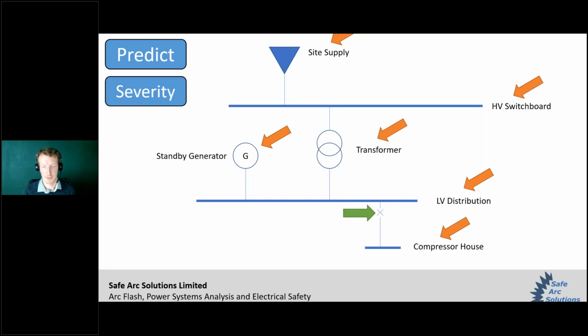And realistically, you also need to think about different configurations of the network. This can really change how the arc flash energy works, depending on whether you're using local generation, relying on the site supply, have multiple sources feeding a different point, and things like that. And what you can see is the green arrow is the circuit breaker that they were closing, that Scott and Sam were closing in our incident example. But to understand specifically what happens at that breaker, you need to have a good understanding of the whole of this network. And so that's where the time often comes.